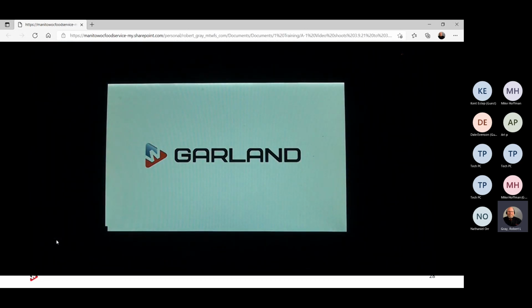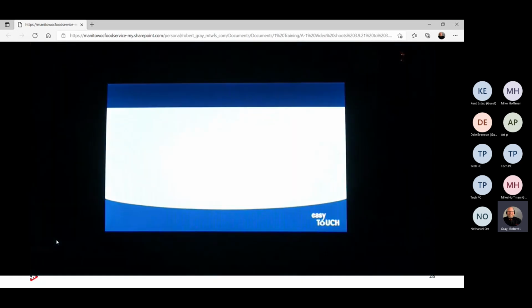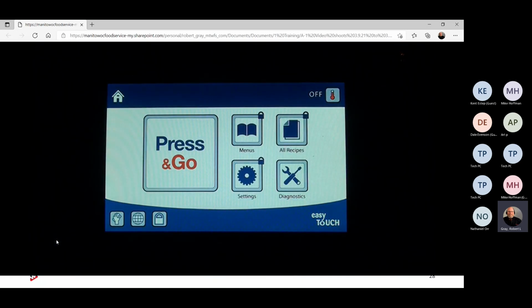So what we did here, we turned on the main power switch and we're waiting for it to go through its process. What it's doing is going into the control contactor, energizing, sending power out through my safety thermostats for each heating zone per lane, back to the coil of the load contactor, sending three-phase power to a solid-state relay, checking thermocouples, checking communications between the boards, and checking to make sure the platen is in the up position. Once it's in the up position, everything checks out, everything's where it's supposed to be. It's going to go to the home screen just like this. Okay, this is indeed the off screen.